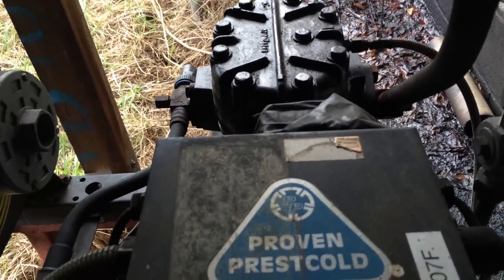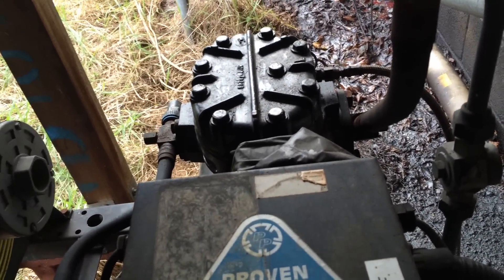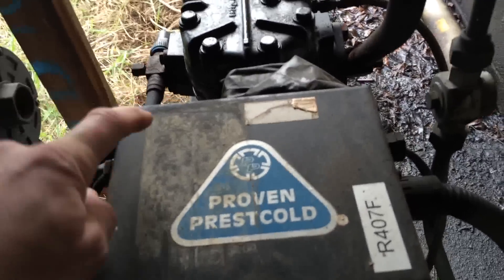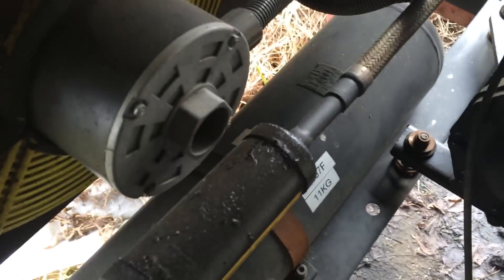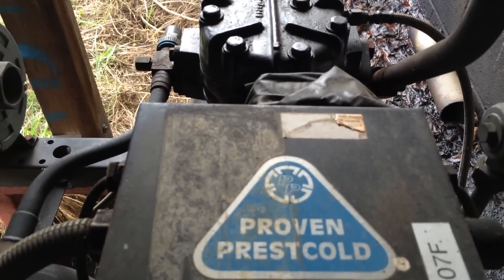I was working on the other unit and I literally thought there was a bit of noise coming from down this end. I wandered down to this unit and then everything had gone off. The main had definitely just tripped - tripped out for the whole site. By turning all the breakers off and me resetting them, it tripped again. But I isolated it to this compressor. Basically it seems to have died while I was here working on the adjacent unit.